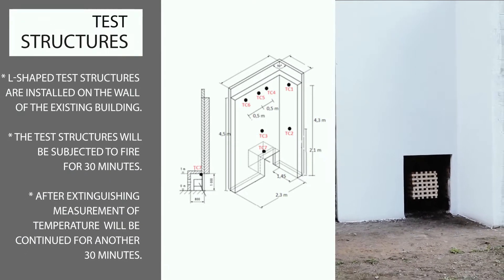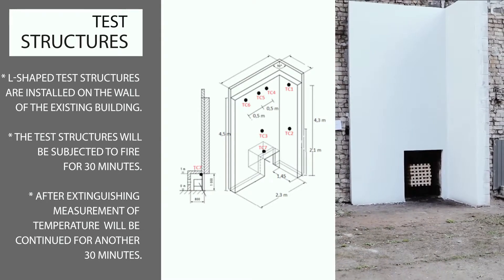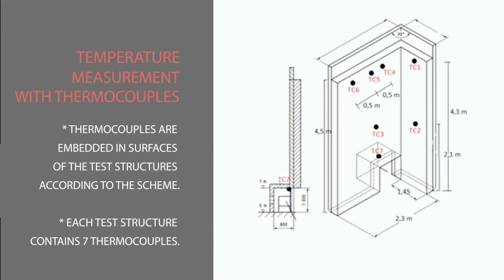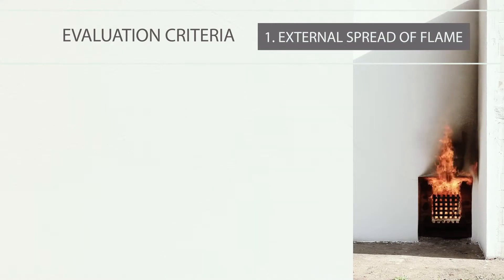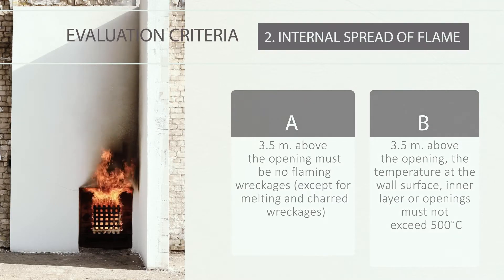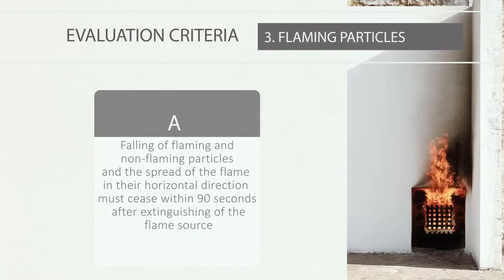L-shaped test structures are completely installed on the wall of the existing building. Test pieces are subjected to fire for 30 minutes. After extinguishing, temperature measurement continues for another 30 minutes. Thermocouples are embedded in surfaces of the test structure. For external spread of flame assessment, at 3.5 meters above the opening there must be no flaming wreckages, no temperature exceeding 500°C, and no continuous burning. For internal spread of flame, at 3.5 meters above the opening there must be no flaming wreckages and no temperature exceeding 500°C. Flaming or non-flaming particles must cease falling within 90 seconds after the flame source is extinguished.